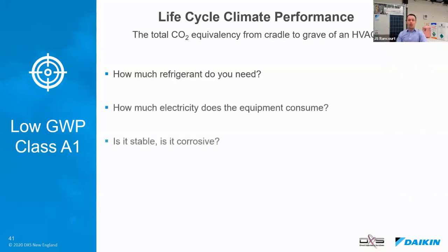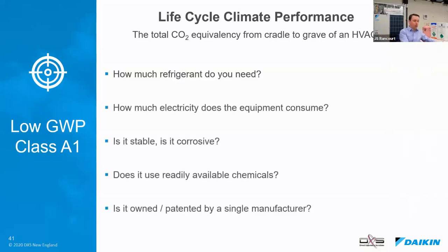You've got to look at how much refrigerant you need. If you find a refrigerant that has less global warming potential, but you need twice as much of it because it can't carry as much heat, then you've lost the battle. If you find a refrigerant that has less GWP, but it's less efficient and the machine is going to consume a bunch more power, especially right now in the US with the emissions of our grid, depending where you are, then you've also lost the battle. Is the refrigerant stable? Is it corrosive? Does it use readily available chemicals? And is it owned or patented by a single manufacturer, unlike R32, which is a non-patented substance that anybody can make?